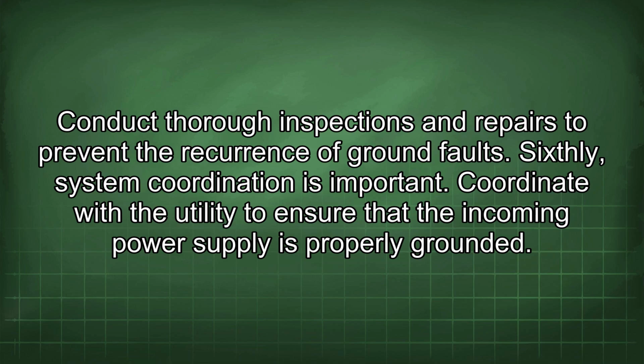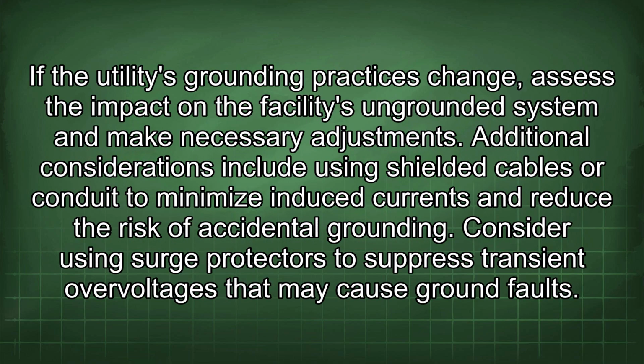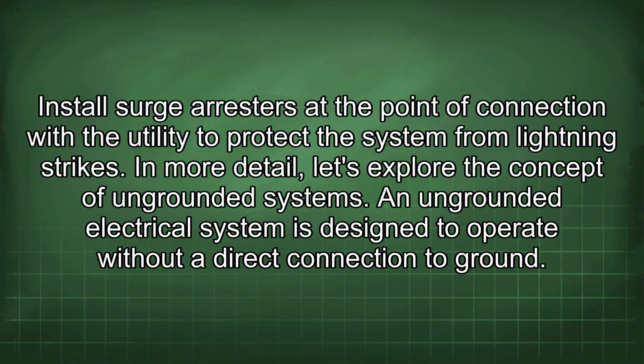Sixthly, system coordination is important. Coordinate with the utility to ensure that the incoming power supply is properly grounded. If the utility's grounding practices change, assess the impact on the facility's ungrounded system and make necessary adjustments. Additional considerations include using shielded cables or conduit to minimize induced currents and reduce the risk of accidental grounding. Consider using surge protectors to suppress transient overvoltages that may cause ground faults. Install surge arresters at the point of connection with the utility to protect the system from lightning strikes.